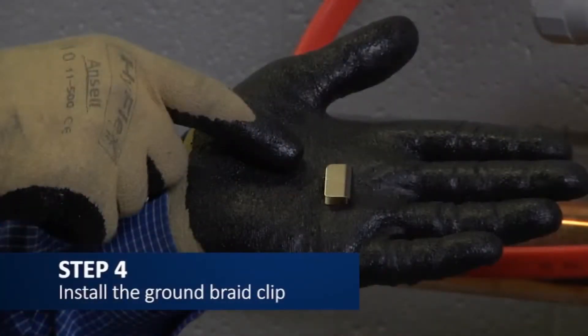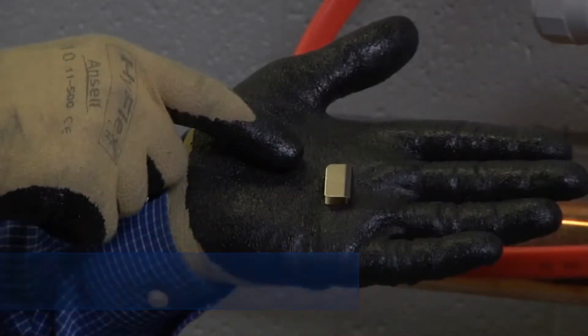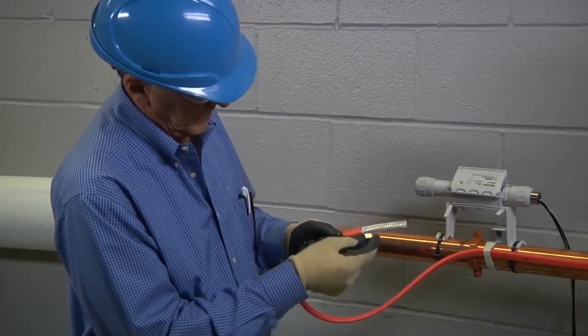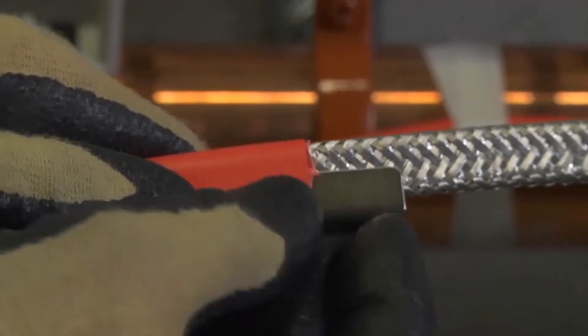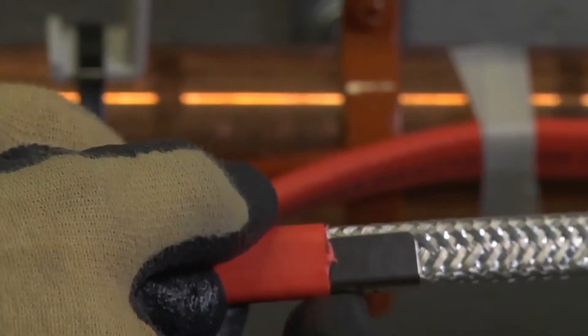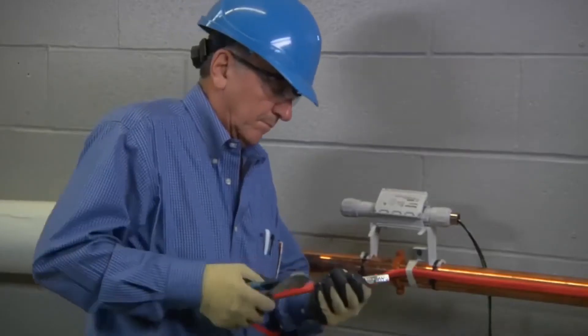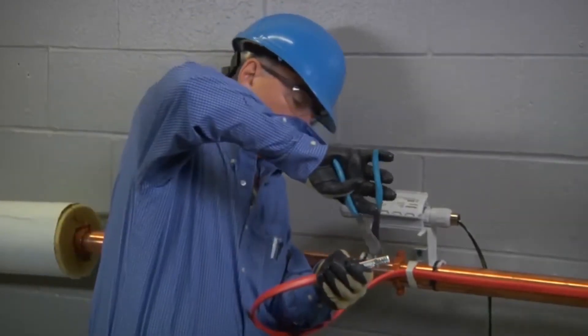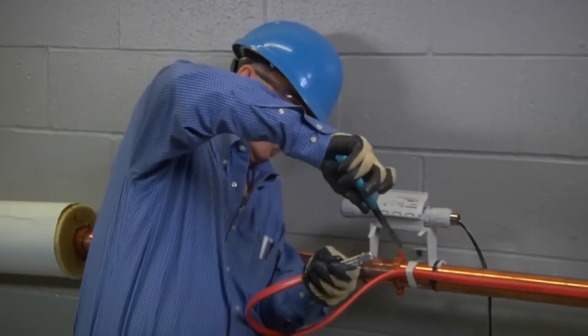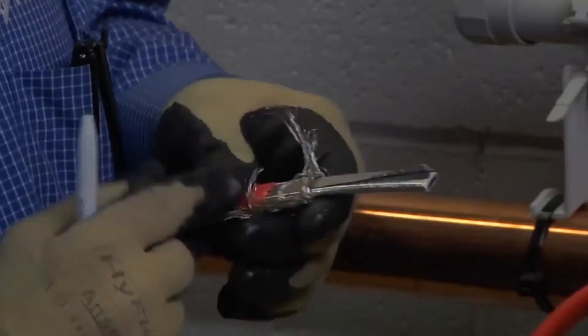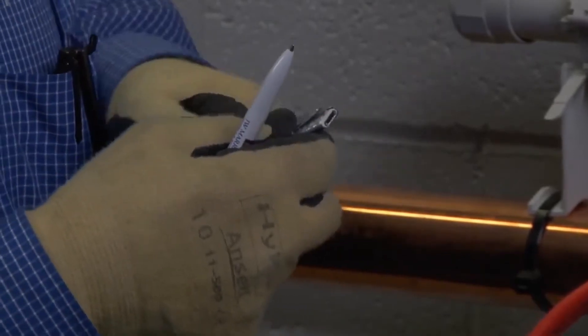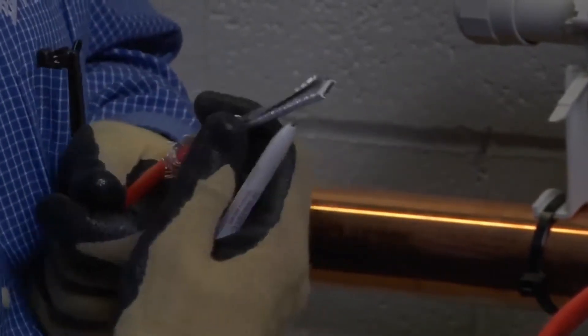Next, install the ground braid clip over the heating cable by pinching it lightly in place using your fingers, and sliding the clip up the cable until it touches the outer jacket. Using your wire cutters, cut away one inch of the ground braid from the end of the heating cable, and pull the exposed braid back over the ground braid clip and the outer jacket.